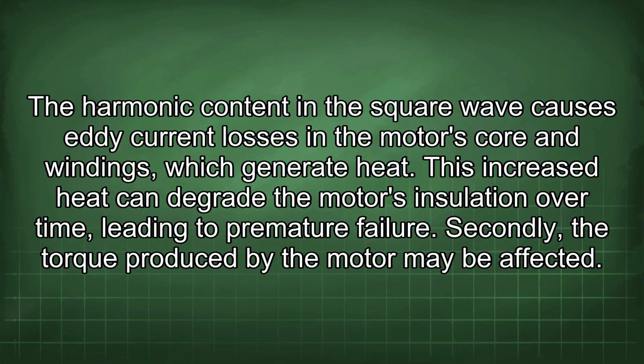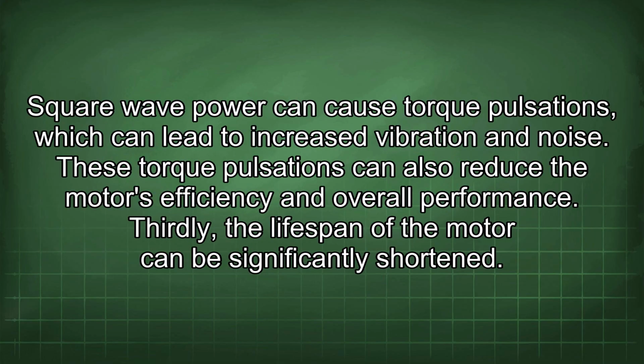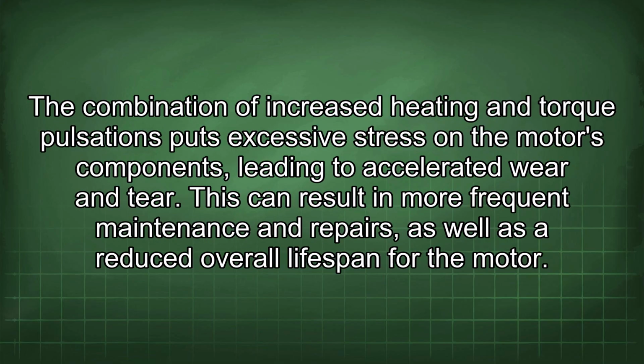Secondly, the torque produced by the motor may be affected. Square wave power can cause torque pulsations, which can lead to increased vibration and noise. These torque pulsations can also reduce the motor's efficiency and overall performance. Thirdly, the lifespan of the motor can be significantly shortened. The combination of increased heating and torque pulsations puts excessive stress on the motor's components, leading to accelerated wear and tear. This can result in more frequent maintenance and repairs, as well as a reduced overall lifespan for the motor.